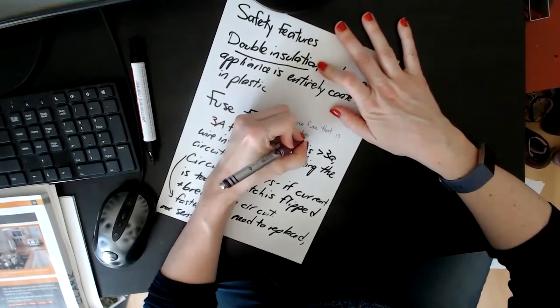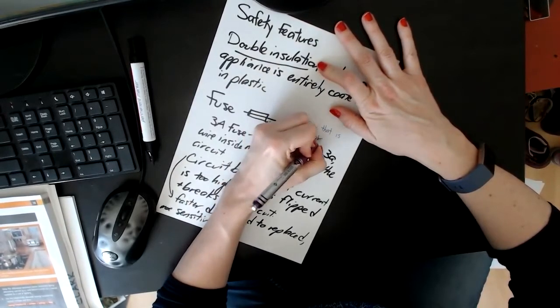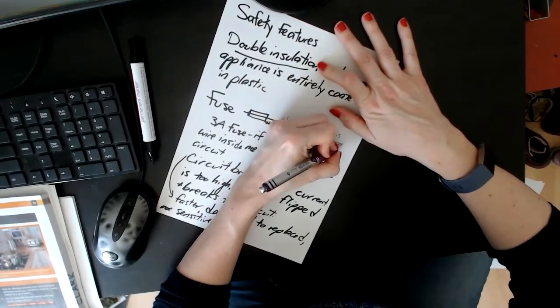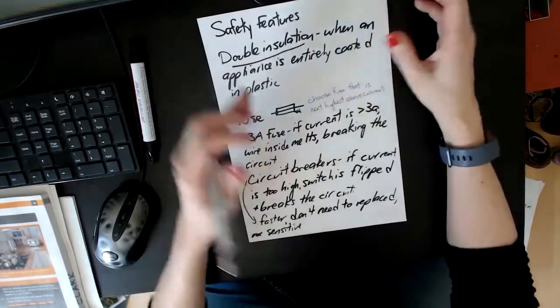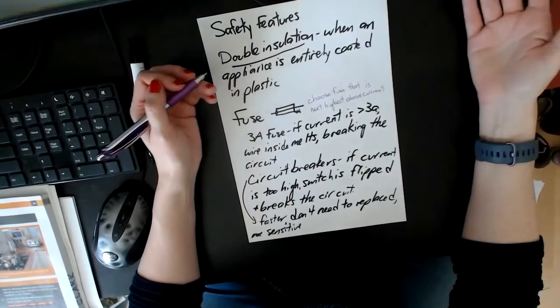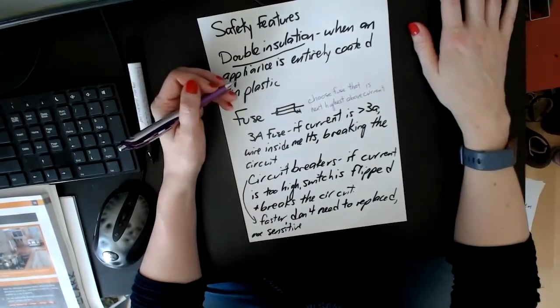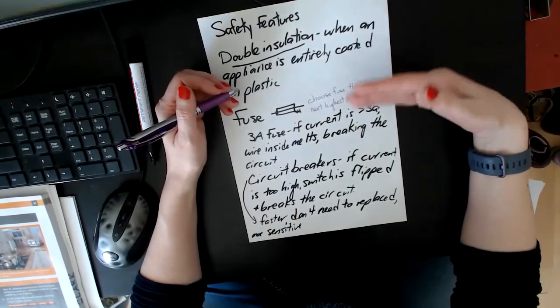So you pick the closest number, but higher. That means if you have a choice between a 7 amp and a 13 amp fuse, and the current flowing through something is 7.5 amps, then you have to get the 13 amp. And that's a big difference.